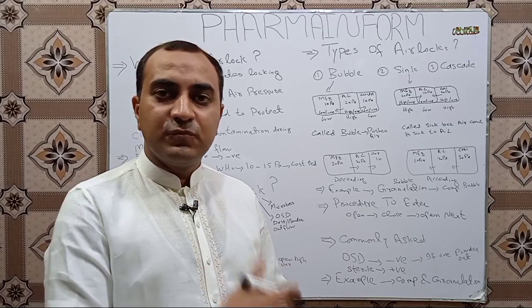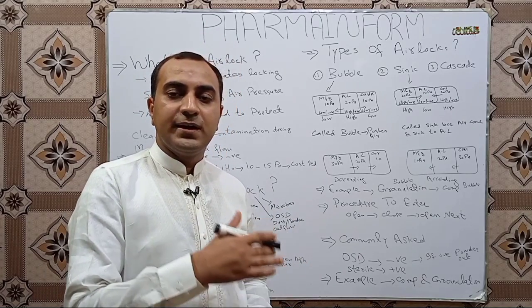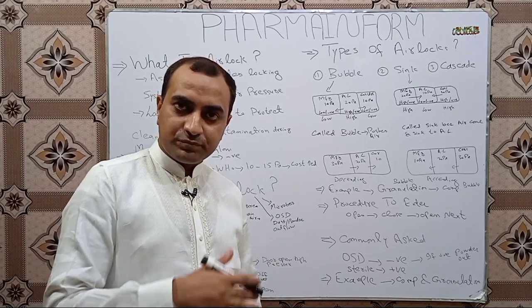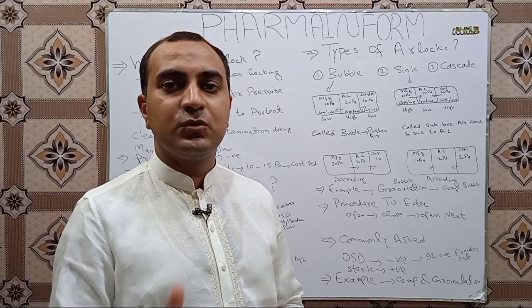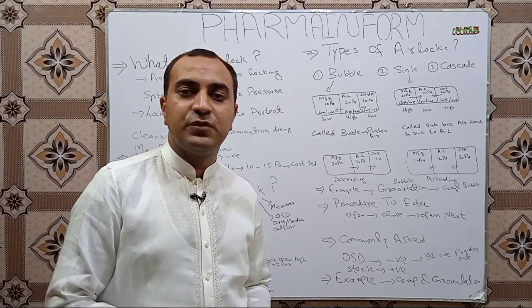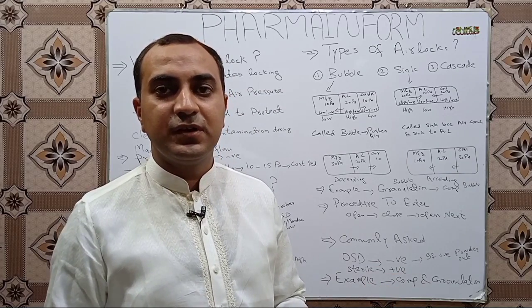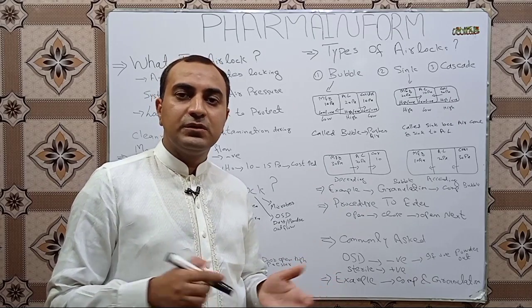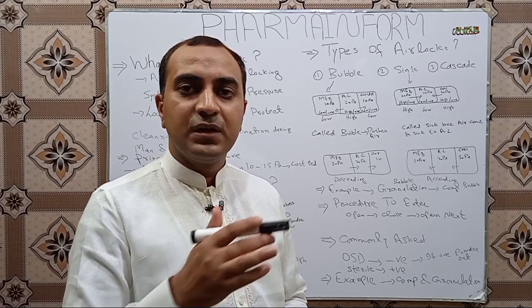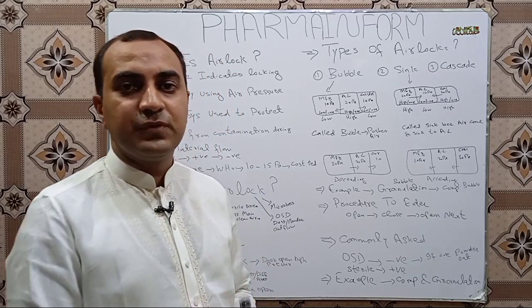We must protect one clean room from another. So we must establish buffers or airlocks — for example, from Grade D to Grade C, we must have an airlock, and from Grade C to Grade B we must have an airlock. Similarly, if we are manufacturing different products in adjacent areas like Granulation A and Granulation B, we must have an airlock between them to prevent cross contamination.